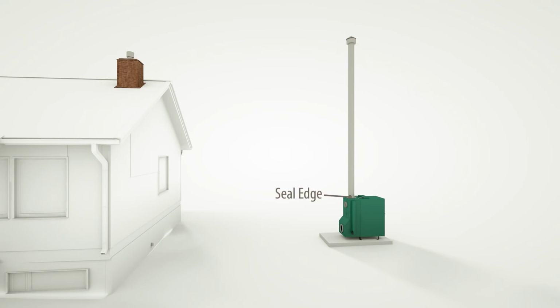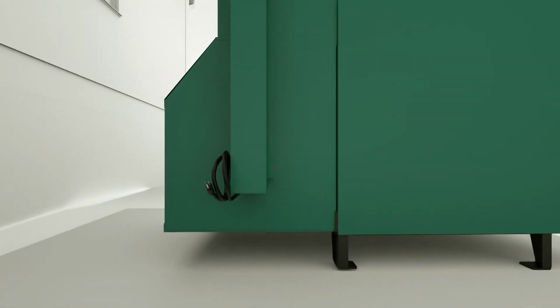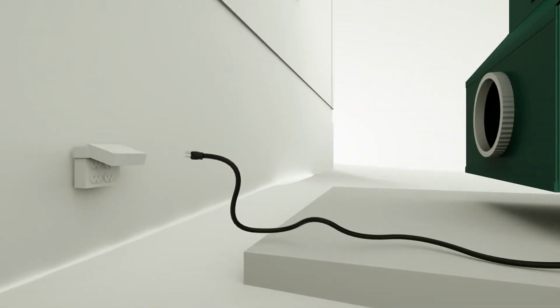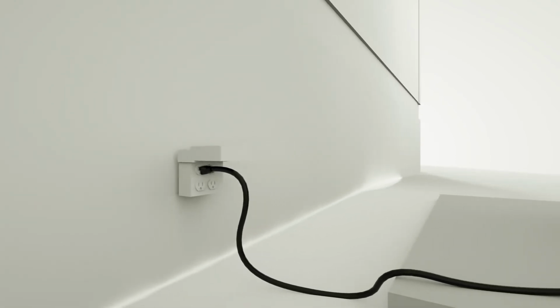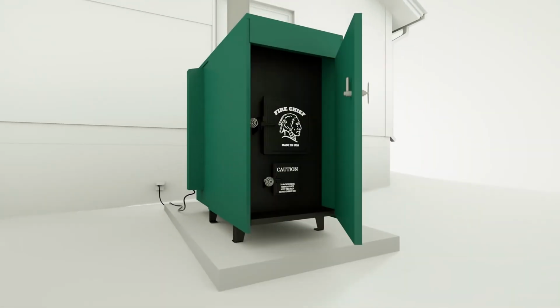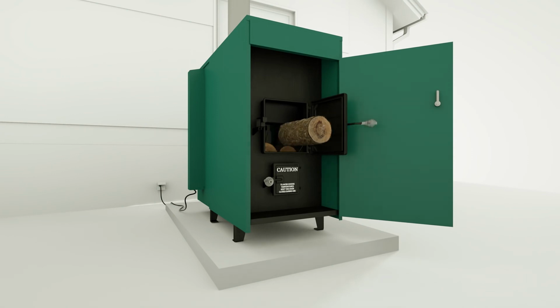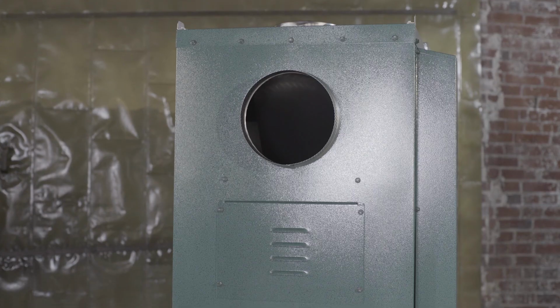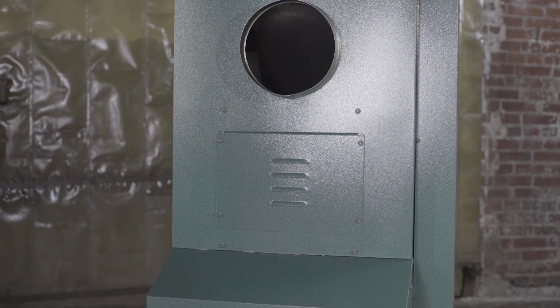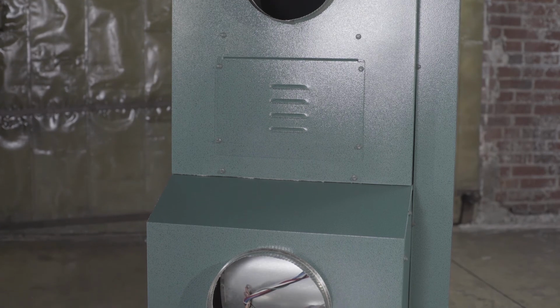Now that the unit is set, the thermostat is wired, and the chimney is connected, you should plug in your furnace. Then, start your first fire in order to burn off the oils used in manufacturing. This will normally take a few hours, but once the unit cools down, you are ready to make the duct connections to your home. You will need to connect the starter collars to both the hot air and the return air vents on your Fire Chief furnace.